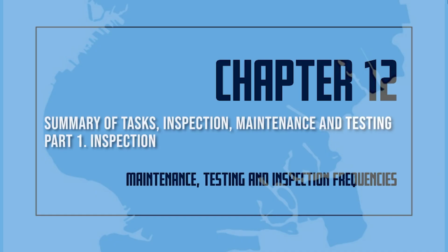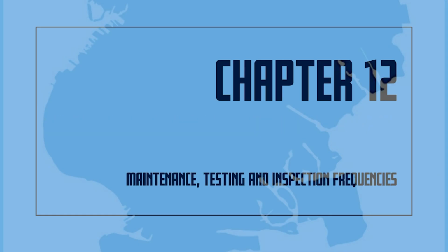A complete summary of tasks of inspection, maintenance, and testing. 1. Inspection. A. Sprinkler systems. Gauges. Dry, pre-action, and deluge systems shall be inspected weekly to ensure that normal air and water pressures are maintained. Where air pressure supervision is connected to a constantly attended location, it shall be inspected monthly.